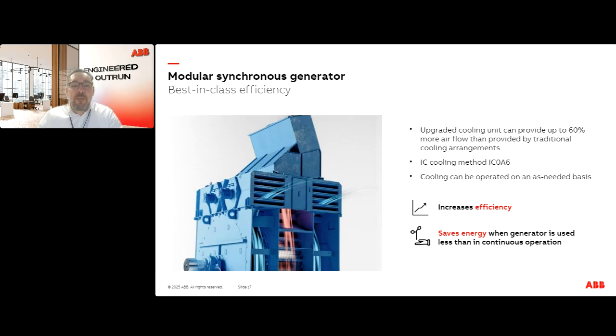And what does that mean? That means that these cooling fans can be connected to frequency converters, so you can run them on demand. When the generator is running cooler, you can leave them off, or run them at a lower RPM and lower power. In that way, you save energy also in the cooling system. And this is a redundant system. Like mentioned, there are four fans, 2 on each side, but you can run even if one fan is not running. You can run the machine with nominal power even with 3 of these cooling fans.